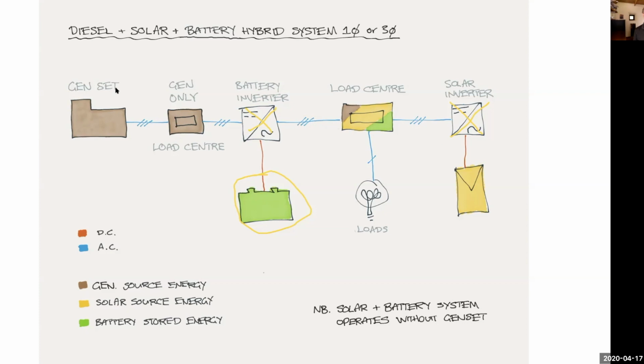Usually what you'd rely on is a generating set. It comes along and makes everything much better - woohoo, automatic start generator or manually started generator. The generator starts up and provides AC power to the battery inverter, which wakes it up, which then wakes up the solar inverter, and we're back in action again.